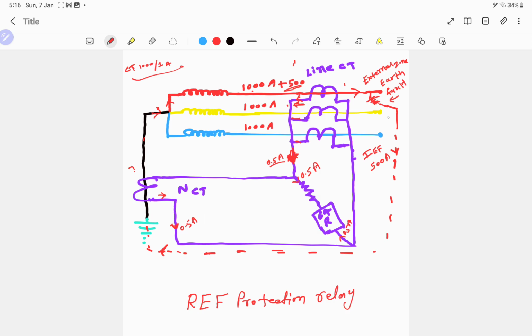Now at the same time, at the earth fault, 500 amp fault current will flow here. It will go through the neutral CT towards the R phase. So it will go through the neutral CT towards the winding. So the secondary current will flow in the opposite direction of the primary current. In a CT, normally the secondary current flows in the opposite direction of the primary current. So it will flow here like this, in this direction.